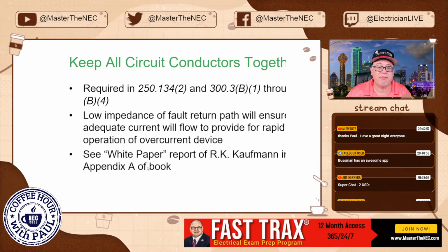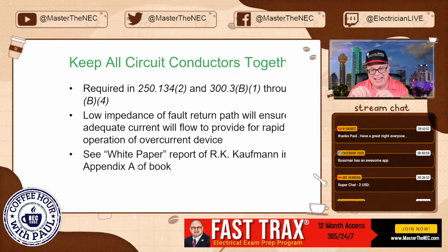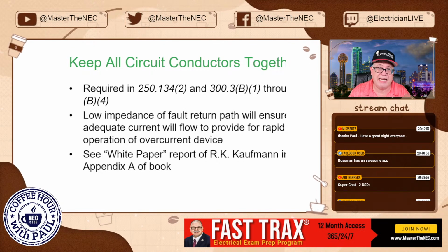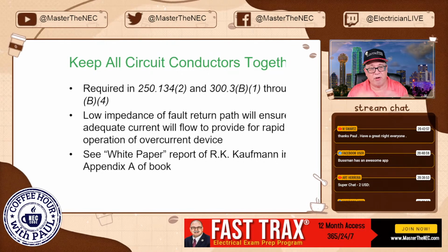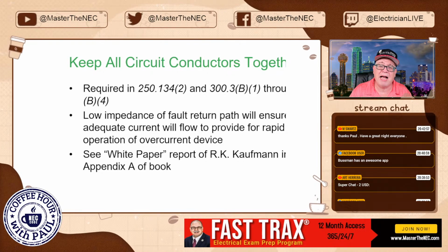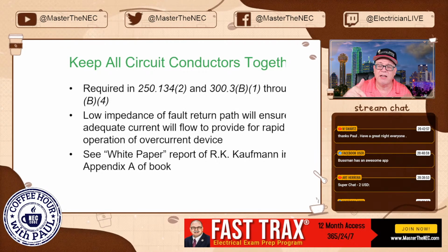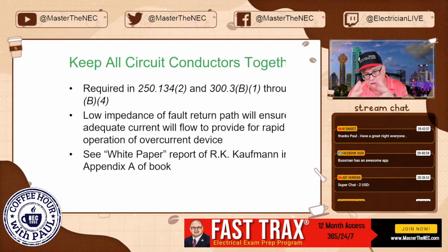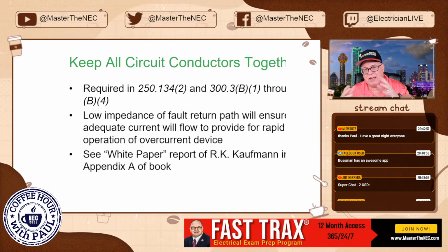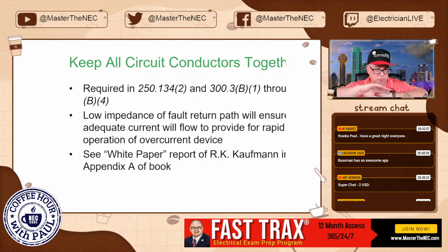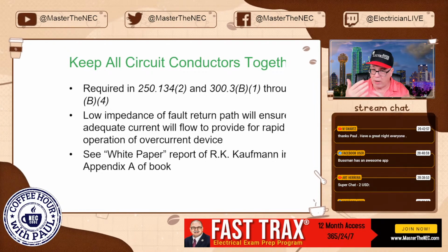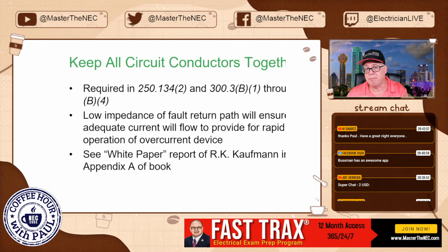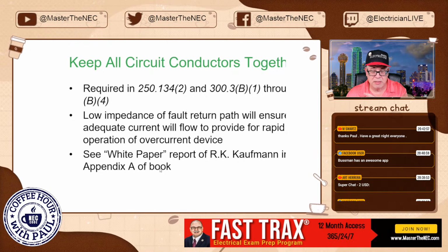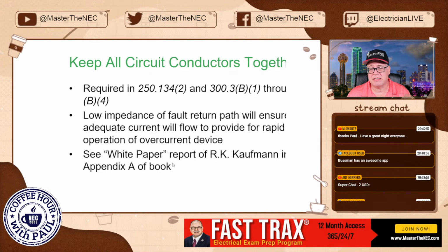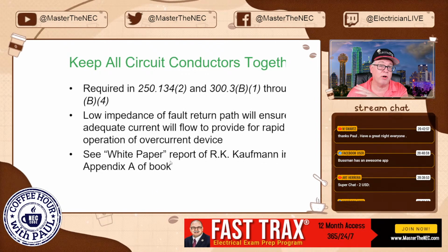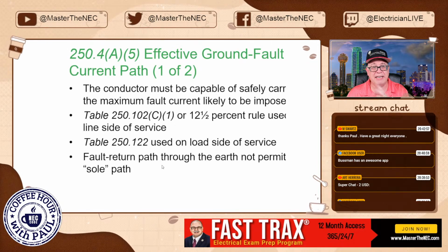And if you want some great information, there's a white paper that's in our grounding and bonding book. Sadly, I can't make that available to you, because you have to have our grounding and bonding course. But it is in there, put out by R.K. Kaufman. It's in the appendix, and it talks about keeping the circuits together, what happens, the inductive heating, and what happens if you separate them. It's an interesting read. So if you've got our grounding and bonding series, the purple series, make sure you check out the appendix and read that. Also, there's the story of the Ufer ground in there as well, for those that are interested.